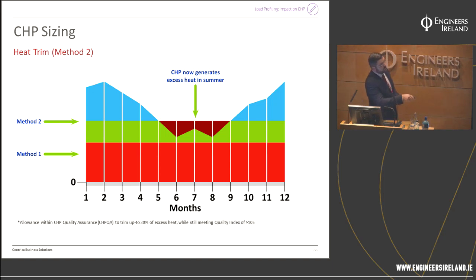The SEAI would show that you can utilize that for a portion of the year, as long as the rest of the year was still within 75%. So if this shaded area was no greater than 25% of the total, it still qualifies for high efficiency CHP. But ideally you don't want that. So this is the hard design time when people need to pick a point between those two and be happy with it on your site.